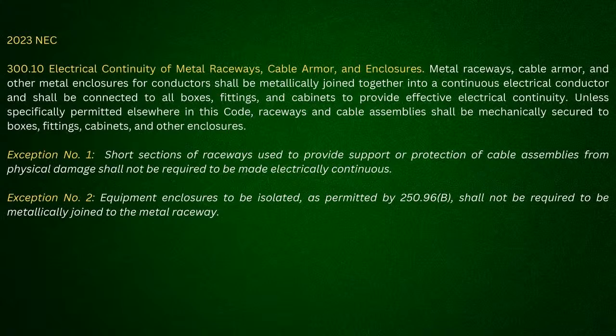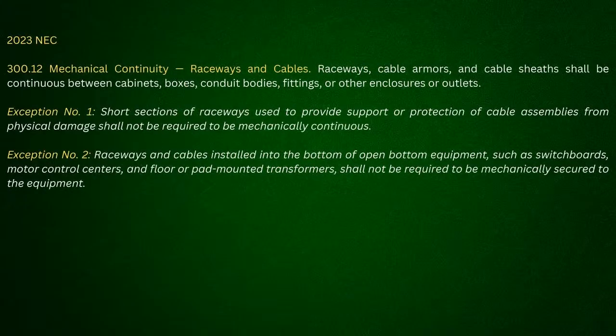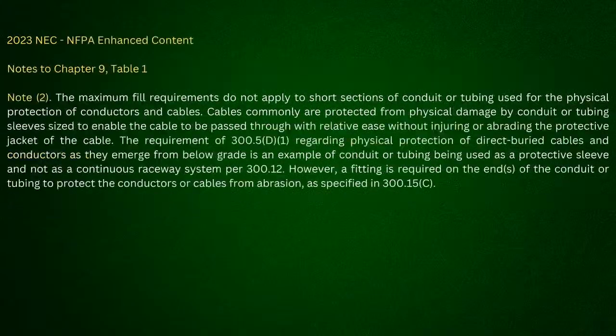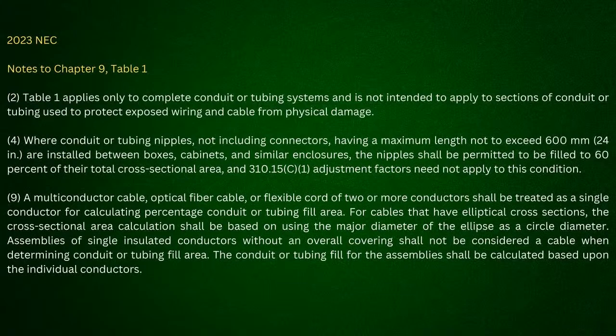Now, if I go to the next one, 300.12, it gets into your raceways and cables. Okay, so look here. Once again, a cable connects from end to end, right? But look there, exception 1 allows me to use EMT, for instance, as what? A short section. So right here, I'm not reading anything into this. I'm showing you where exception number 1 here in 300.10 and 12 comes back and matches right here with the short sections that they're describing here in note 2 to Chapter 9, Table 1.